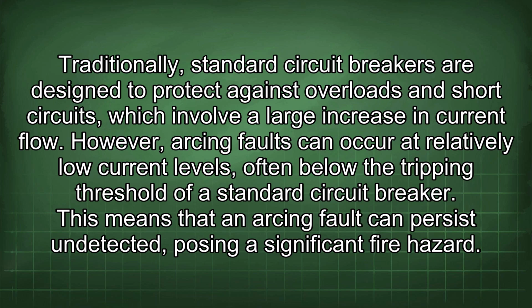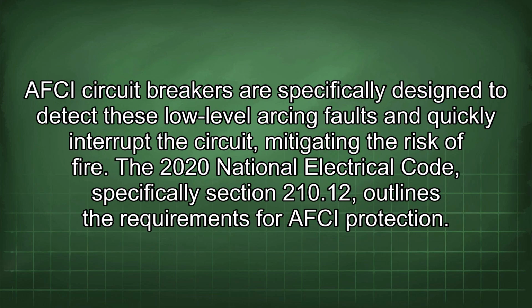Traditionally, standard circuit breakers are designed to protect against overloads and short circuits, which involve a large increase in current flow. However, arcing faults can occur at relatively low current levels, often below the tripping threshold of a standard circuit breaker. This means that an arcing fault can persist undetected, posing a significant fire hazard. AFCI circuit breakers are specifically designed to detect these low-level arcing faults and quickly interrupt the circuit, mitigating the risk of fire. The 2020 National Electrical Code, specifically Section 210.12, outlines the requirements for AFCI protection.